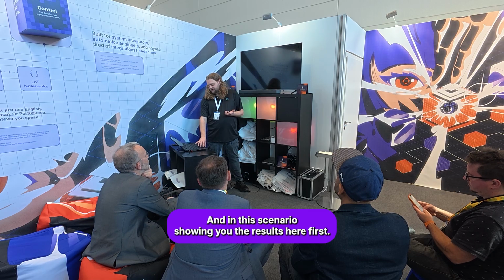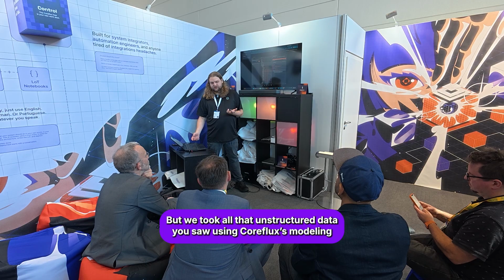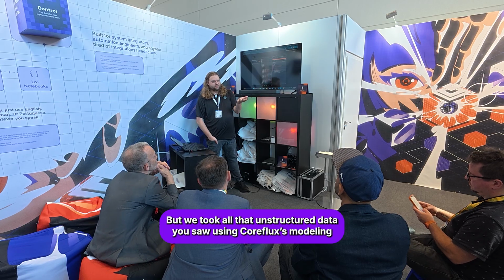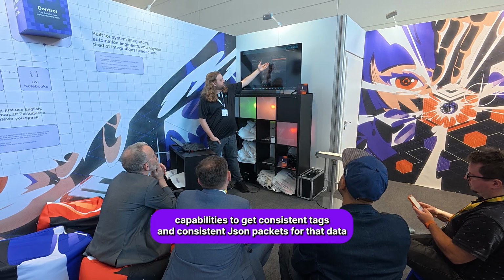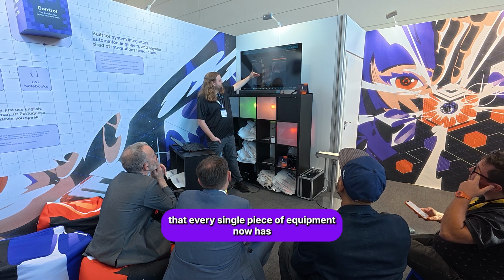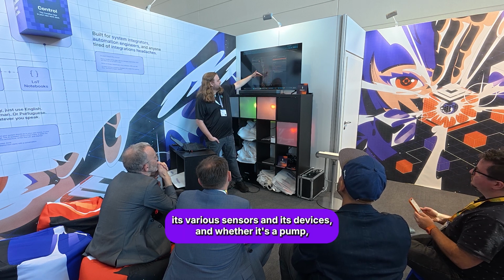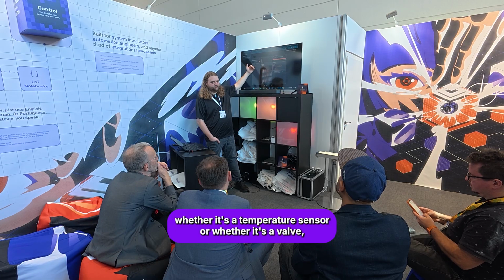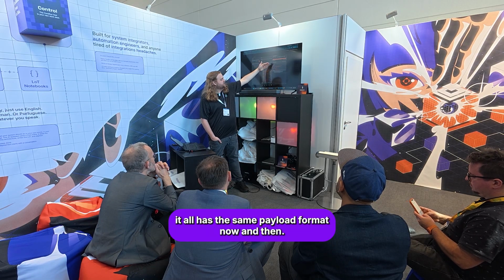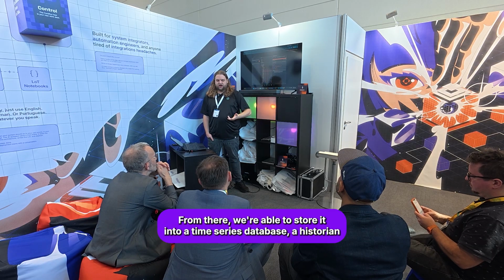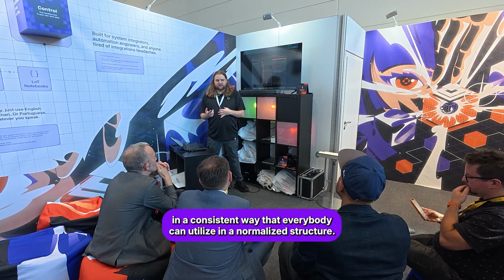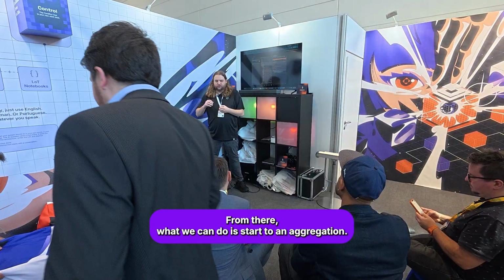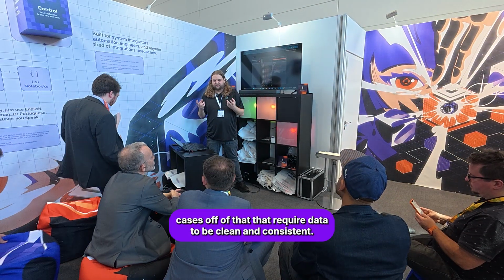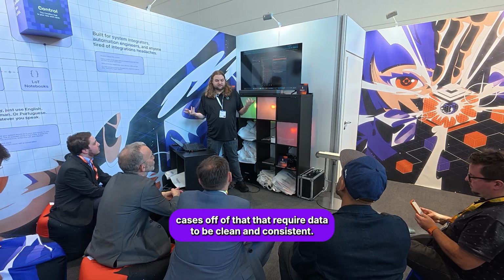In this scenario, I'm showing you the results here first, but we took all that unstructured data you saw using Coreflux's modeling capabilities to get consistent tags and consistent JSON packets for that data. Every single piece of equipment now has its various sensors and devices, and whether it's a pump, a temperature sensor, or a valve, it all has the same payload format now. And then from there, we're able to store it into a time series database, a historian, in a consistent way that everybody can utilize in a normalized structure, from which we can start doing aggregation. We can start doing use cases that require data to be clean and consistent.